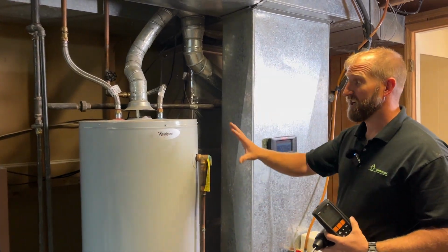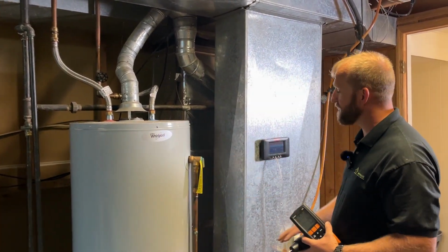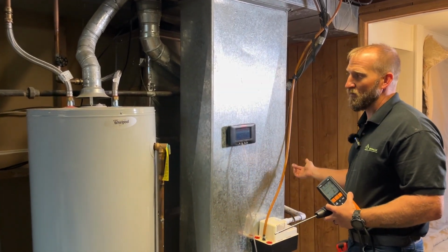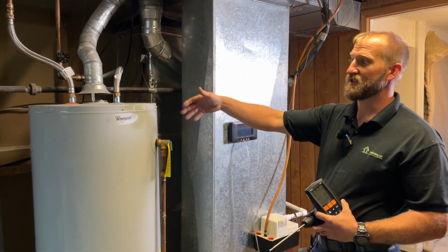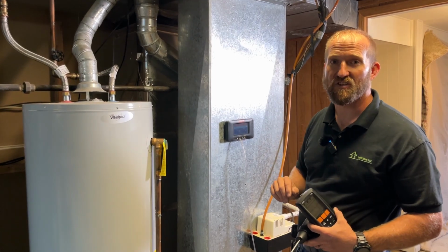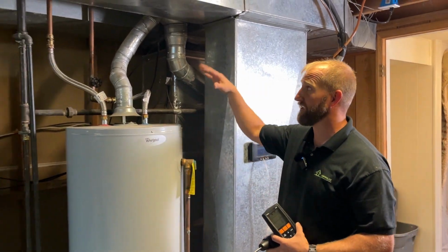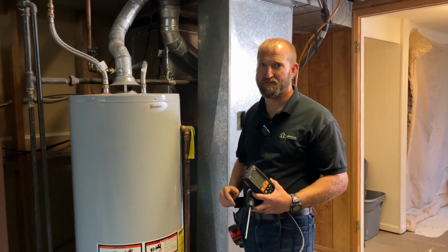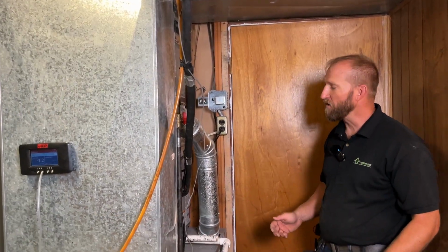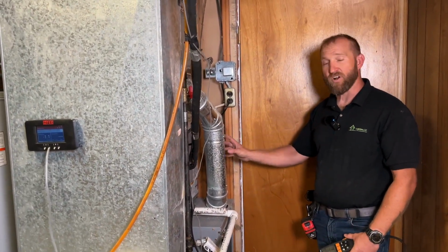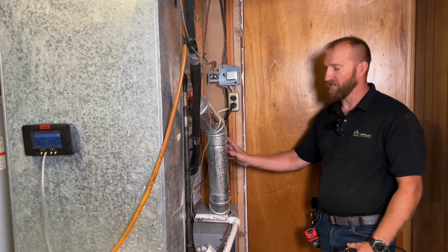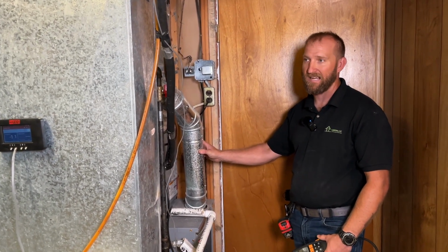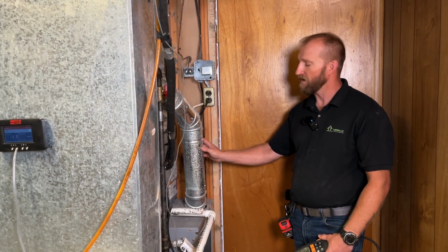You want to test the lowest BTU unit first, then the higher BTU unit, being the furnace. So now we would kick the furnace on, and make sure we're still not backdrafting once the furnace kicks on, because that can, depending on the flue configuration, cause the water heater to now backdraft. So when you're testing a furnace, if there's already a port drilled in it from the testing of the HVAC guys, you can utilize that port.